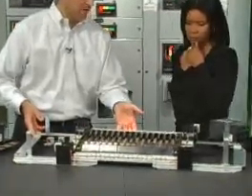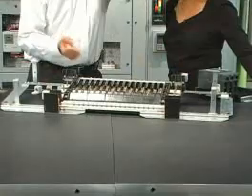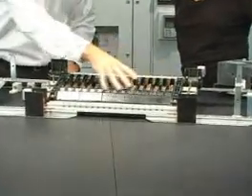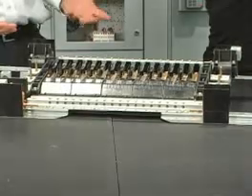This is a copy of a blank interior. And from here you can see it's got an asymmetrical design, so you can mount it top or bottom, doesn't matter. So it's very easy at the job site. It's got a blank area for all of our branch devices. And then it's got some studs here at the end. And what the studs are for is for either a main lug kit or a main circuit breaker kit. What we've got today is a main circuit breaker kit.